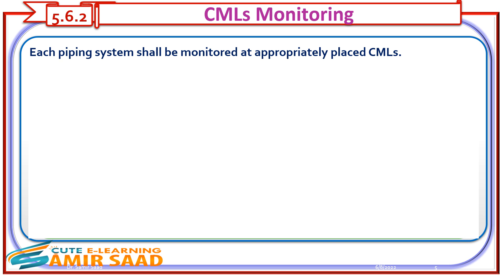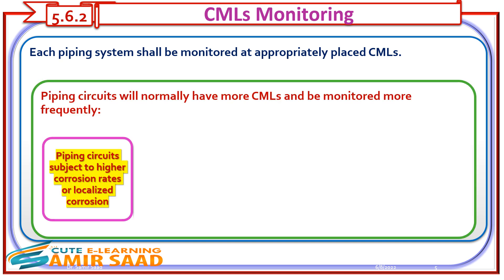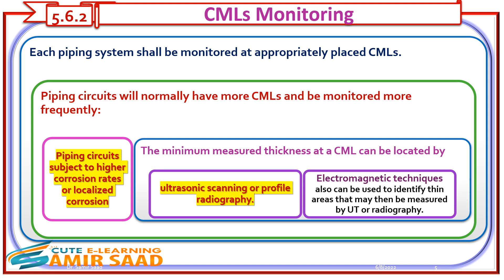Each piping system shall be monitored at appropriately placed CMLs. Piping circuits will normally have more CMLs and be monitored more frequently if they are subject to higher corrosion rates or localized corrosion. The minimum measured thickness at a CML can be located by ultrasonic scanning or profile radiography. Electromagnetic techniques can also be used to identify thin areas that may then be measured by UT or radiography.